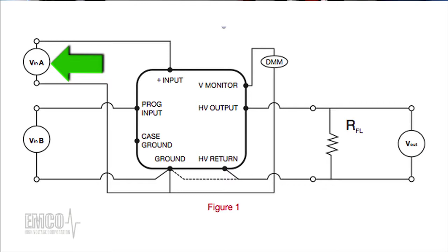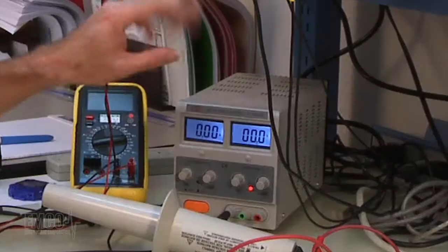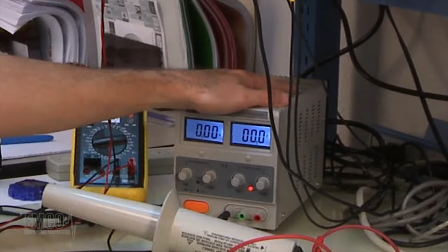To test a regulated model, you'll need a few pieces of test equipment. In the application note, we refer to Vin A power supply, which is the main input voltage power supply that provides power to the unit to operate from. It needs to be rated to apply the appropriate voltage and input current as stated on the data sheet, so be sure you have a power supply capable of providing power to that module.